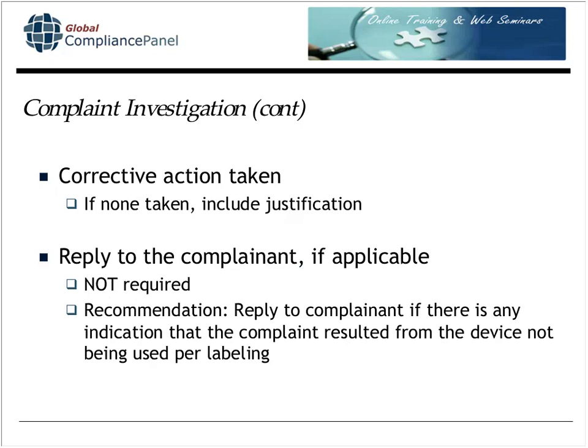Your complaint investigation should then include what corrective action has been taken or will be taken. What many firms I know do on their investigation report is document the corrective action that will be taken, and they document the ECO, or engineering change order, or DCO, or ECN, what have you, number. Although the corrective action has not occurred yet, you've reserved an engineering change document number that will contain the corrective action as it's taken, enabling a link to be provided from the investigation report to the corrective action.